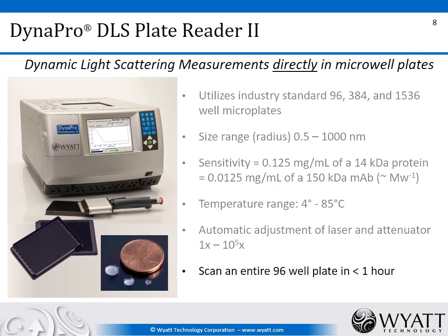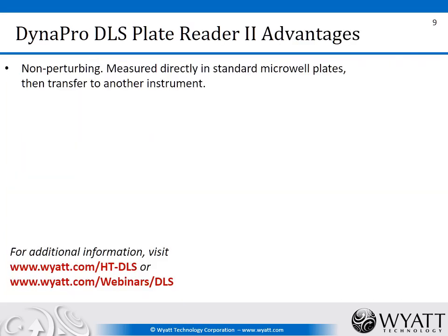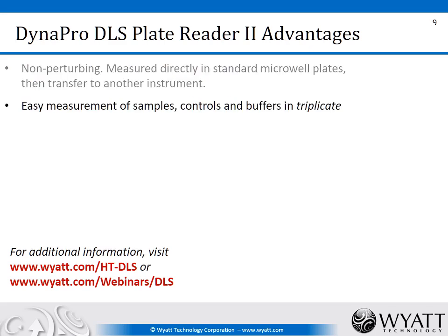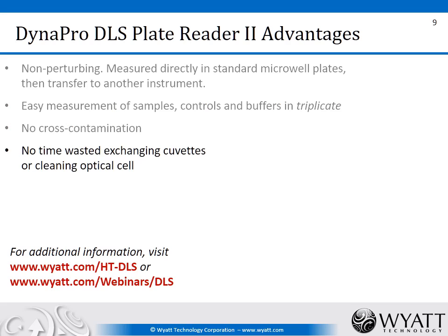You can scan an entire 96-well plate in less than an hour. The advantages of making measurements with the DLS plate reader include: it's a non-perturbing technique; measurements are made in standard microwell plates; you can recover the sample or transfer the plate to another instrument such as a fluorescence detector. Because you can load up the plate with many samples, it's easy to make robust measurements including controls, buffers, and replicates — triplicates, quadruplicates as you like. There is no cross-contamination, no pipetting out and back in, no fluid transfer, and everything is done in place.